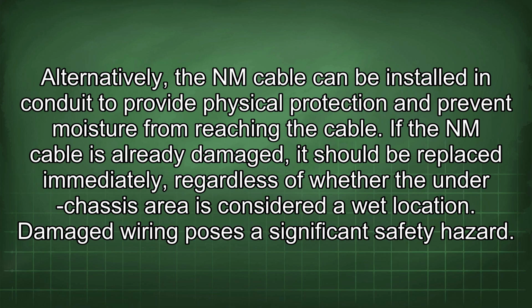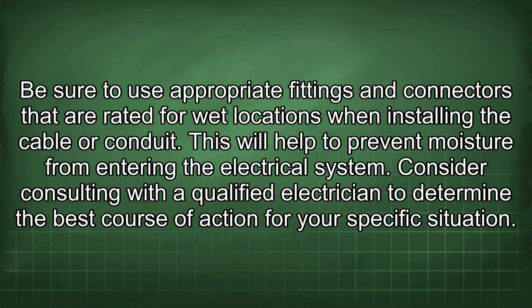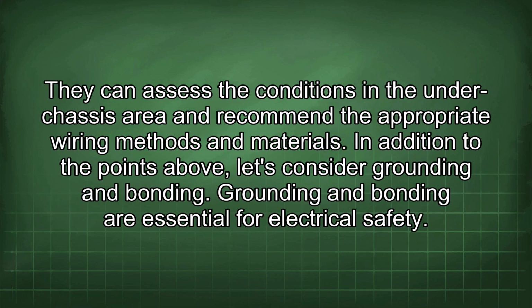If the NM cable is already damaged, it should be replaced immediately, regardless of whether the under-chassis area is considered a wet location. Damaged wiring poses a significant safety hazard. Be sure to use appropriate fittings and connectors that are rated for wet locations when installing the cable or conduit. This will help to prevent moisture from entering the electrical system. Consider consulting with a qualified electrician to determine the best course of action for your specific situation. They can assess the conditions in the under-chassis area and recommend the appropriate wiring methods and materials.